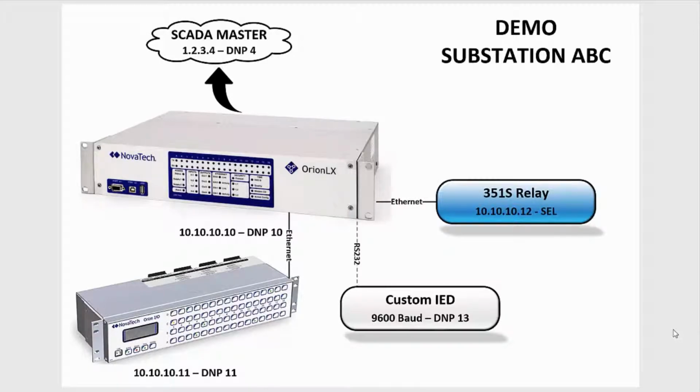Finally, all of the data from these three IEDs are forwarded into the Novatech Orion real-time database, which converts all data into the DNP3 protocol to be sent on to the SCADA master located at 1234 or a DNP address of 4.